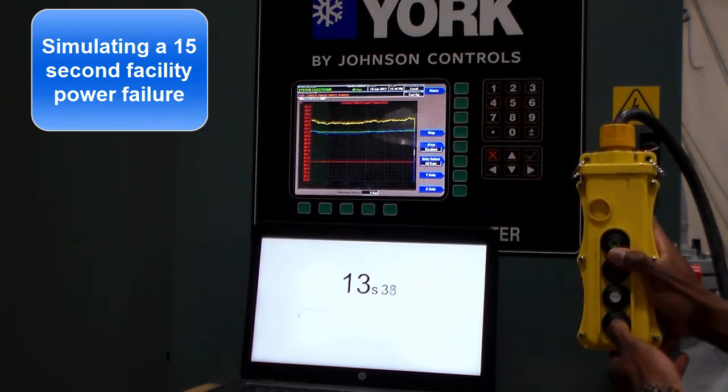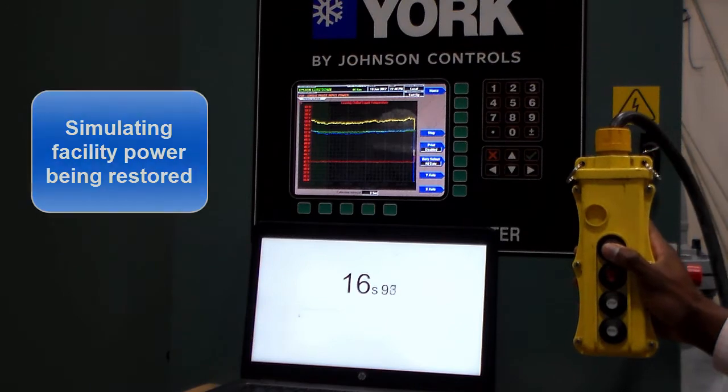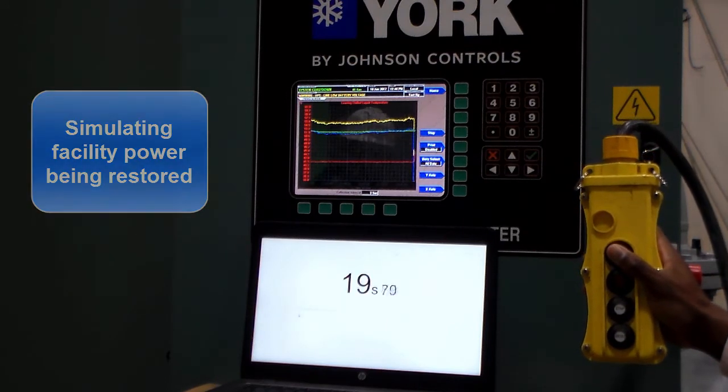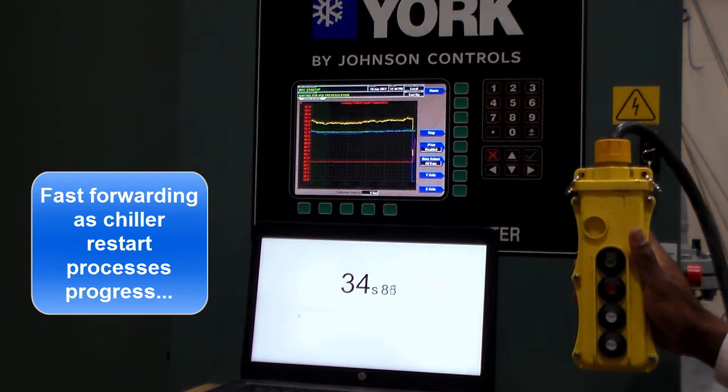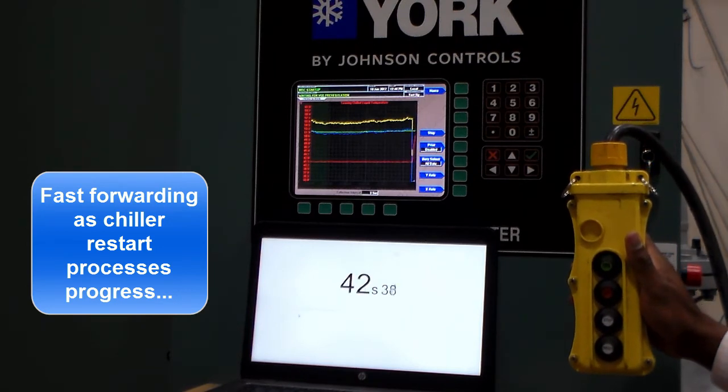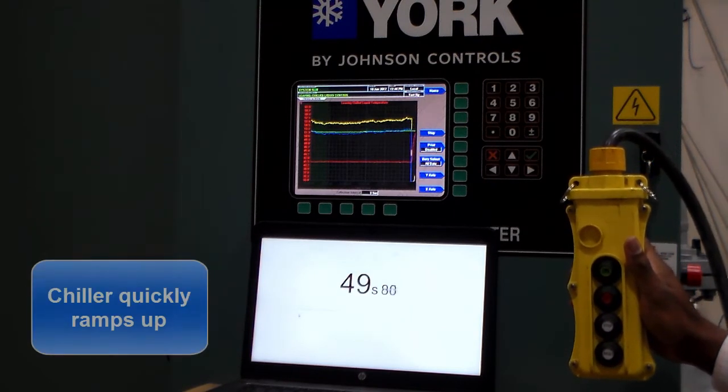So power was cut at 0 seconds and restored at the 17-second mark. Then, after going through a few safety checks and startup processes, the chiller starts ramping up and begins making chilled water about half a minute later at the 50-second mark.